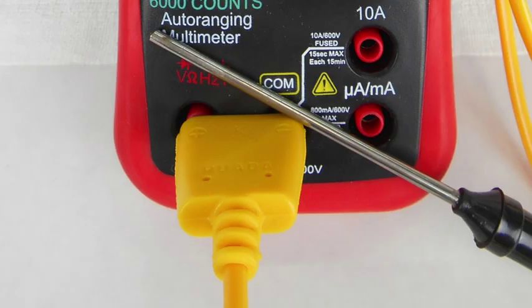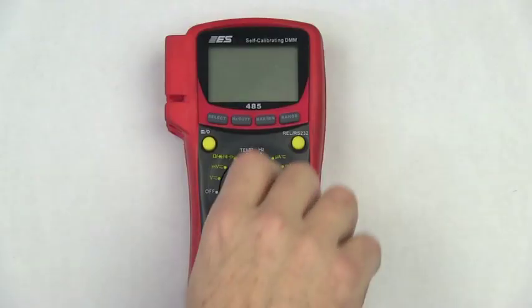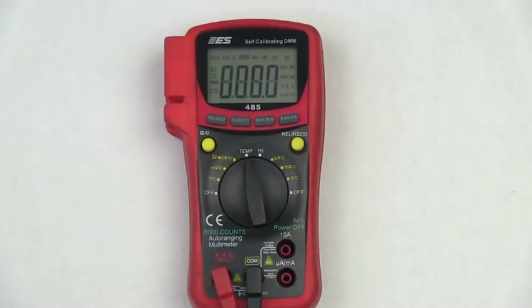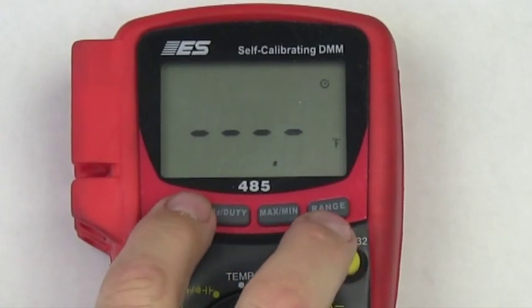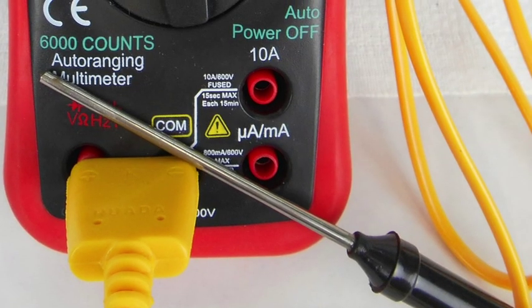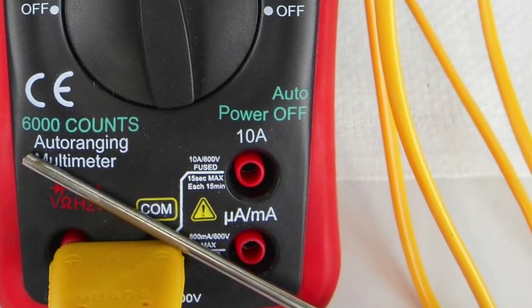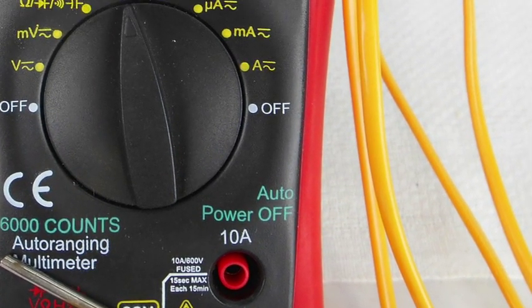The K-type thermocouple temperature probe is connected, with correct polarity, to the common and leftmost meter port. Select the temp setting, and to change to and from Fahrenheit and Celsius, use the Select button. The probe can withstand up to 1292 Fahrenheit, but the cable cannot.